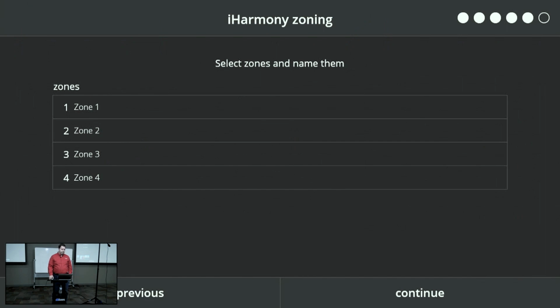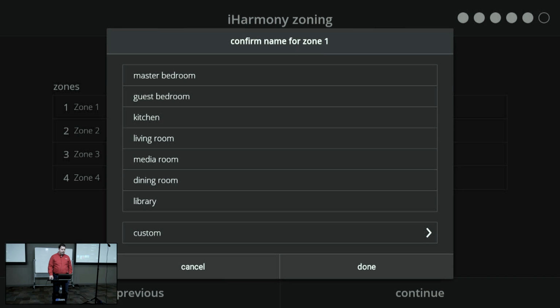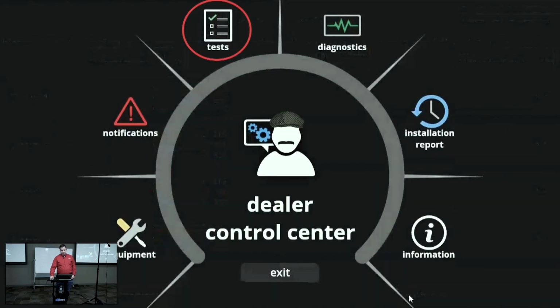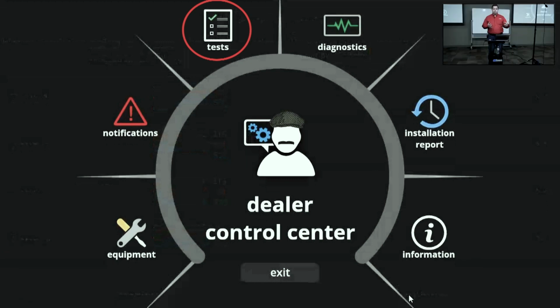This is just reminders. Again, that's not something that's really critical. Here's where we can name your individual zones. You can just select one of those and edit it. When we get into this screen in the Dealer Control Center, you'll have your test screen. You'll also have the diagnostics there. That diagnostic screen is really, really critical in checking out the discharge air sensor. When you select that diagnostic screen, that can be used here at this point in initial startup. It can be used as the system's running.